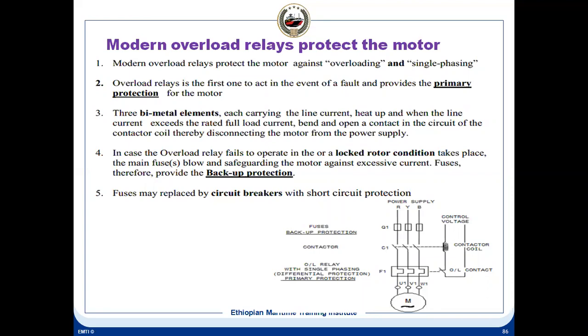So in case an overload relay fails to operate, or locked rotor conditions take place, the main fuse will blow, safeguarding the motor against the excessive current. This is called fuse backup protection. Fuses may also be replaced by circuit breakers with short circuit protection.